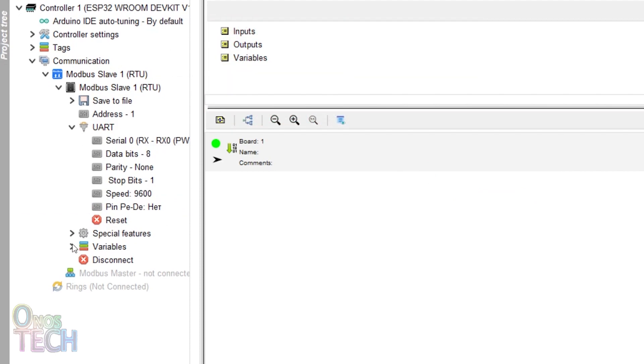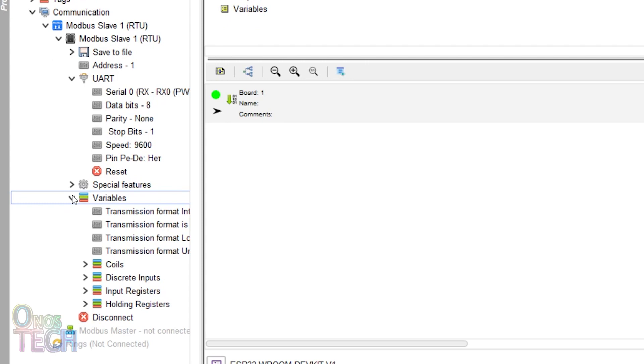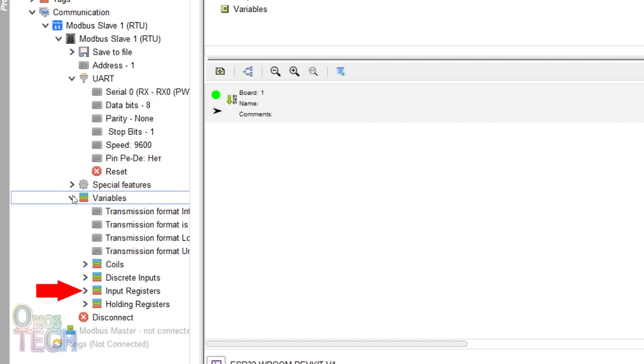Modbus data types under variables are grouped as coils, to read from and write to digital outputs and variables. To read digital inputs and variables, discrete inputs are required. Input registers are used to read from analog inputs and variables, while holding registers read from and write to analog variables.